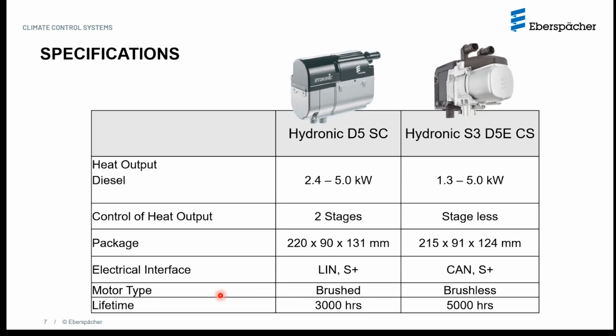So now let's talk about the specifications of both the first generation heater and the third generation Hydronic heaters. As you can see, the name is common. Hydronic applies to both first and third generation, but you can see the description is slightly varied. The first generation was simply described as a Hydronic D5SC heater. The D in the description stands for the type of fuel that the heater uses. So obviously in both cases, you can see the letter D is used for diesel. Number 5 is the output of the heater, the maximum output. So that reflects the maximum output as shown in the table. 5 kilowatt, which is about 17,000 BTU.